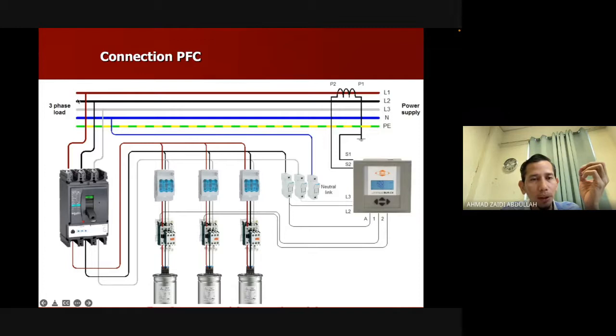And then at another point, you calculate the IC max total and so on, and this is the item. You calculate IC for every step, step 1, 2, 3 up to 6, and lastly the IC total, the IC max total, that you have calculated. This item is the biggest one. This is the breaker value, and the breaker is connected directly to the supply voltage. The breaker can be connected directly. Then the output from the breaker connects to a fuse or a small MCB, an MCB for every step, then to the contactor, and then to the capacitor. It repeats for every step like that.